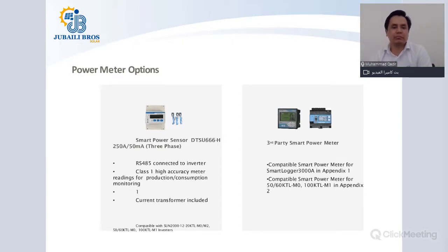Power meters. On the left, you can see there is a smart power sensor. This is a Huawei power sensor. It communicates via RS485, connects directly to the inverter or to the smart logger. It comes with a class 1 accuracy, and it comes with the current transformer included.